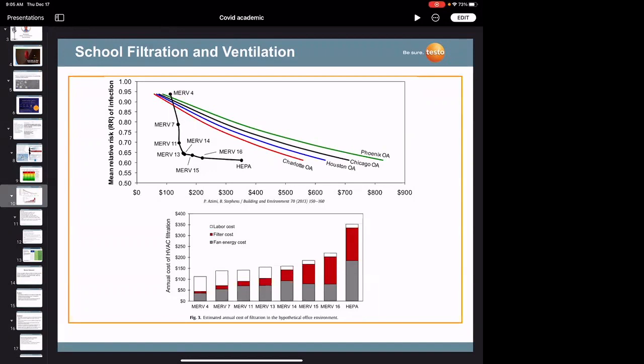The ASHRAE guideline also states that if you absolutely cannot put in a MERV 13 filter, you need to go out and purchase individual portable HEPA filter units and place them in the classrooms. Same thing if you can't afford to put in a brand new systemic relative humidity control system: depending on your location, whether southeast or southwest, you deal with lack of humidity, so you must put in a portable humidifier system in each classroom to keep the humidity constant. In the southeast, you want to put in portable dehumidification units in each classroom if you cannot accommodate it in your current HVAC system.